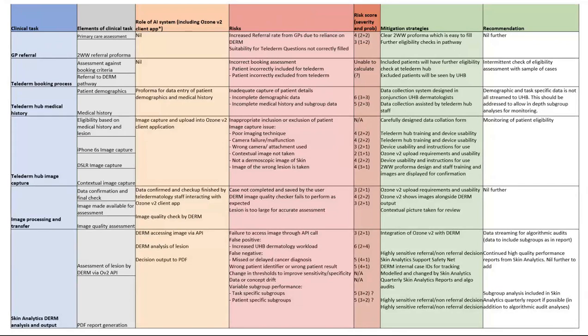manufacturer to actually find the most important risks, which we assign risk priority numbers based on their severity, probability, and the likelihood of them being detected if the errors were to arise. And then that allows us to start thinking about mitigation strategies, but also design our test phase and prioritize. If you just go next, Jeff.